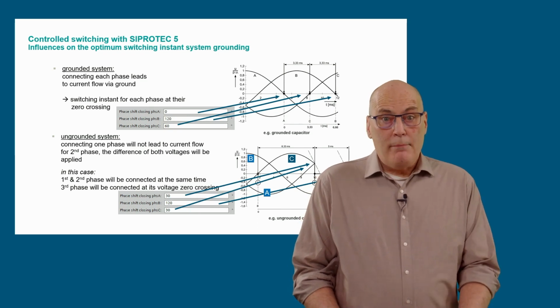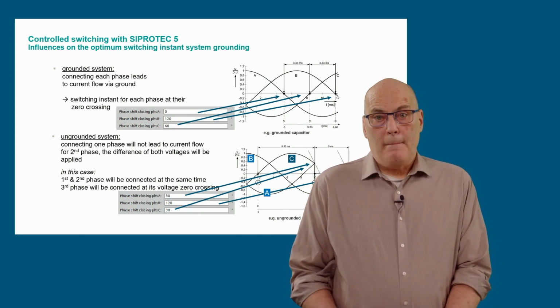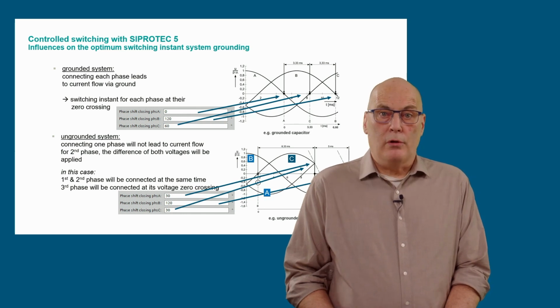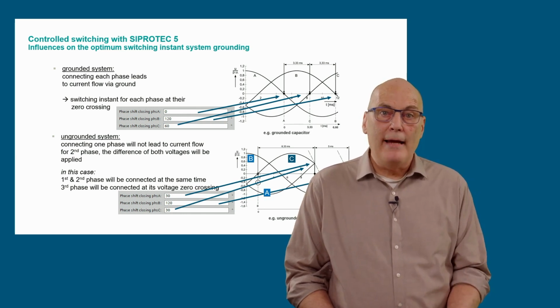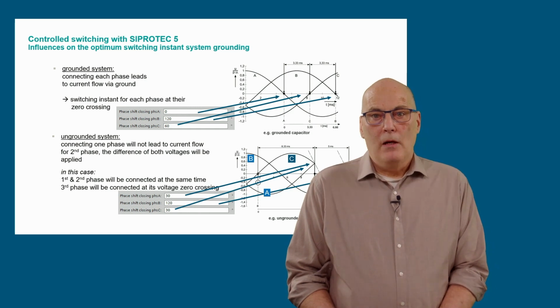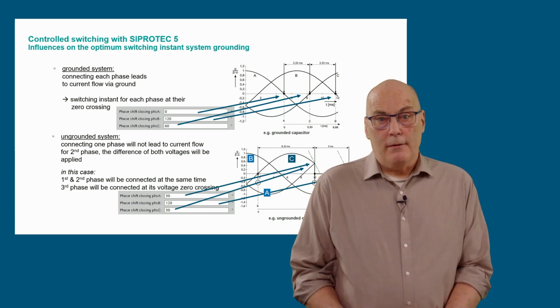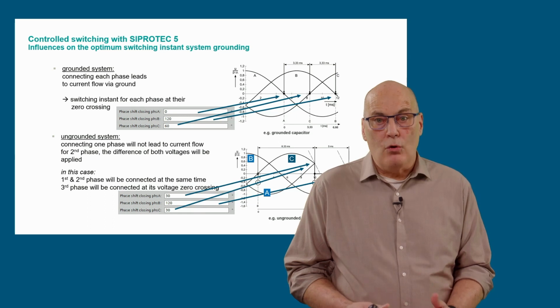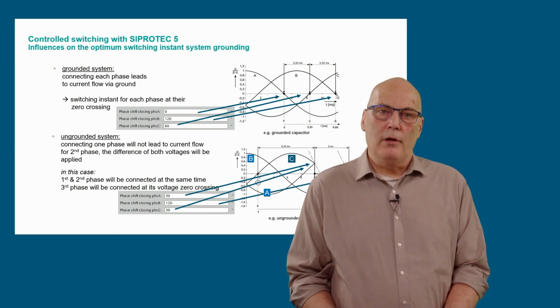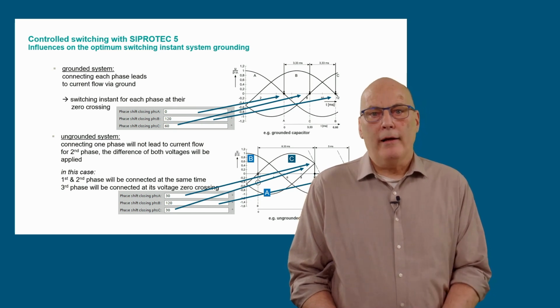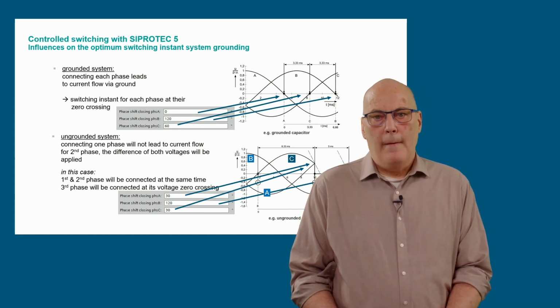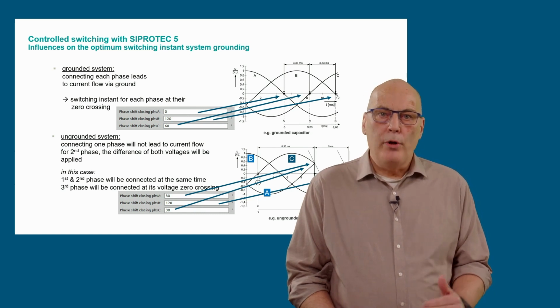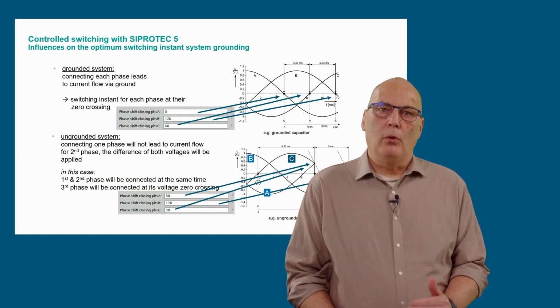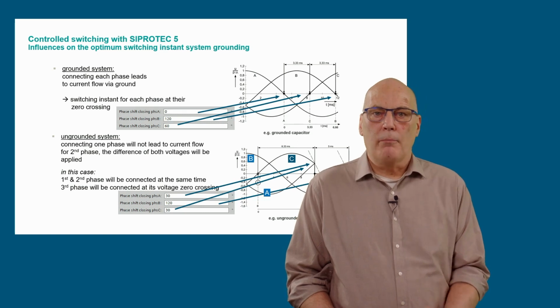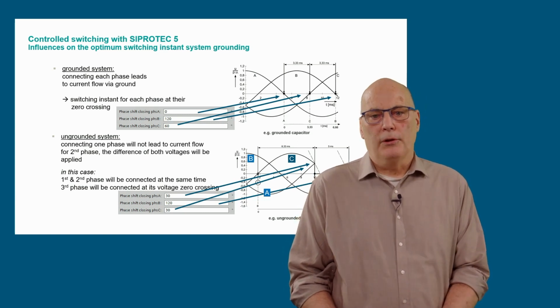The grounded capacitor at the top is different. Here the phase A will be first to close at the zero crossing of the A phase reference voltage. For the grounded capacitor this is correct because the A phase capacitance to ground will have 0 volt before closing. The other poles at the top close in succession at their corresponding zero crossings. Note how the arrows point to the instance of closing each pole and how the angle setting corresponds to the phase A reference voltage.